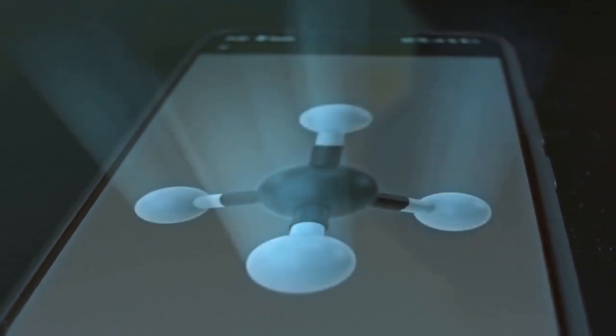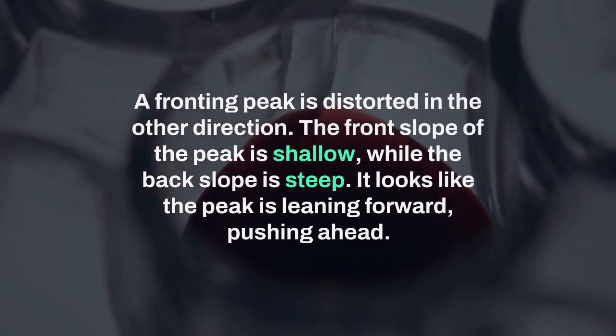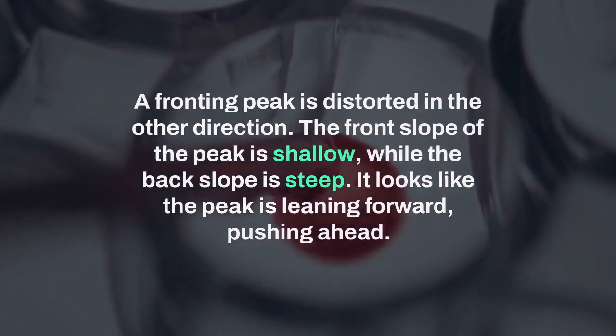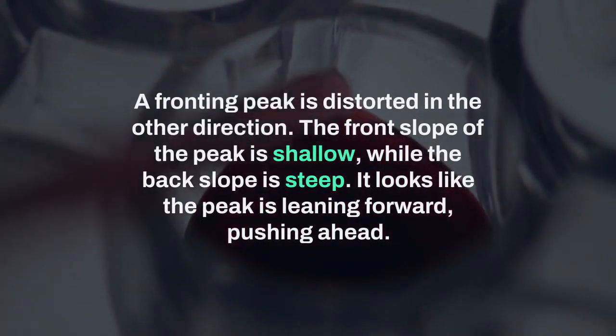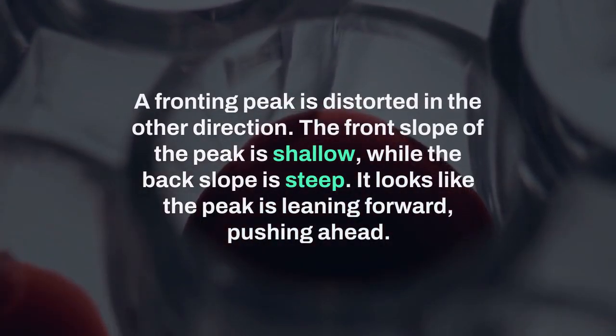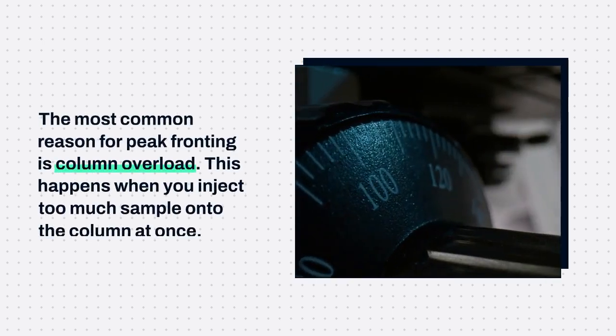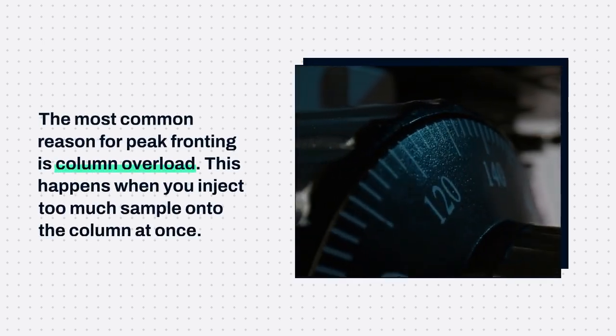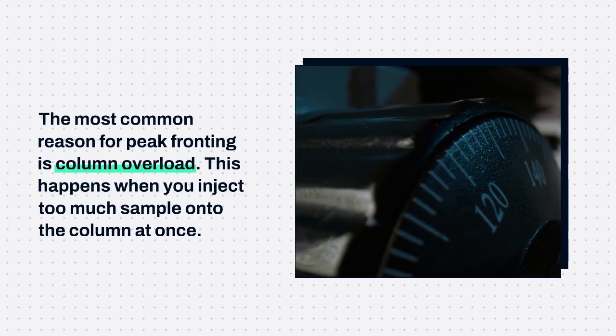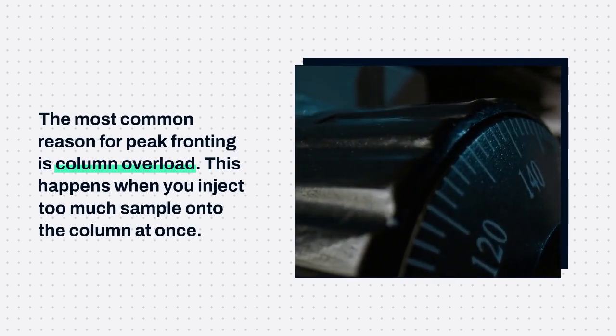Now, let's discuss the opposite problem, which is peak fronting. A fronting peak is distorted in the other direction. The front slope of the peak is shallow, while the back slope is steep. It looks like the peak is leaning forward, pushing ahead. The most common reason for peak fronting is column overload. This happens when you inject too much sample onto the column at once.